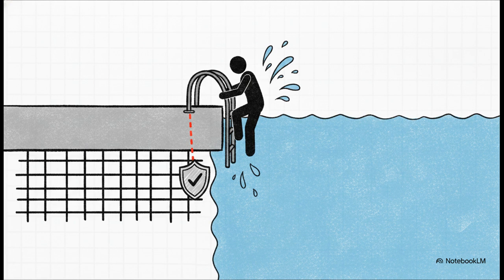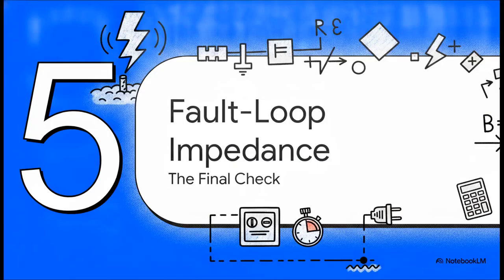Climbing out of a swimming pool, dripping wet, and grabbing a metal pool ladder that just happens to have a slight voltage difference from the wet concrete you're currently standing on. Wet skin has drastically lower electrical resistance. Bonding ties the ladder and the reinforcing steel in the concrete together, completely equalizing the voltage and neutralizing that deadly risk. It's a lifesaver. Which brings us to our last stop, Section 5, Earth Fault Loop Impedance, the final check.